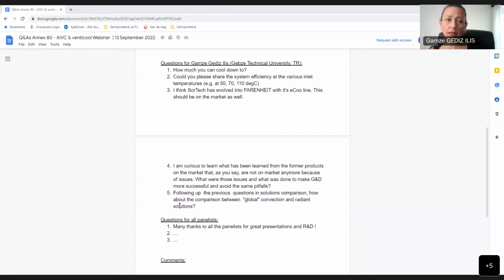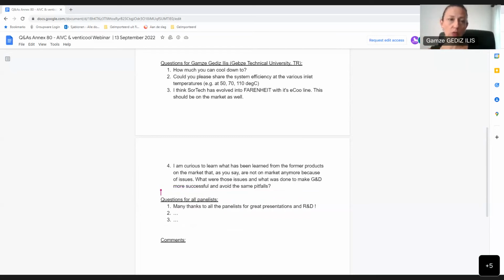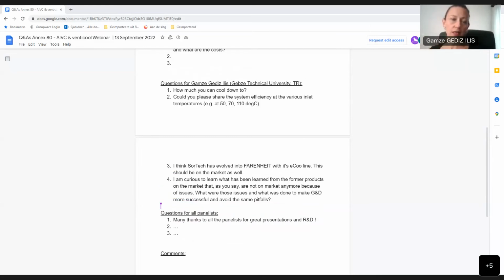But we reduced the size and weight of the absorption chiller. This was important because when transporting such a huge chiller system, it could be 60 kilowatt cooling capacity or 250 kilowatt cooling capacity, the size could increase to 3 or 5 meters long, something like that. So transportation is cheaper with this design, that answers the third question.